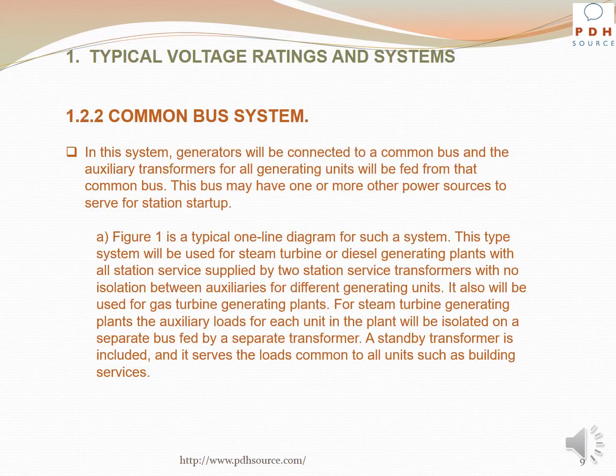In the common bus system, generators will be connected to a common bus, and the auxiliary transformers for all generating units will be fed from that common bus. This bus may have one or more power sources to serve for station startup. Figure 1 is a typical one-line diagram for such a system. This type of system will be used for steam turbine or diesel generating plants with all station service supplied by two station service transformers with no isolation between auxiliaries for different generating units. It also will be used for gas turbine generating plants.